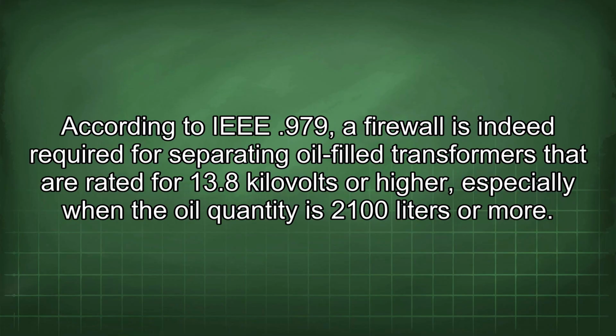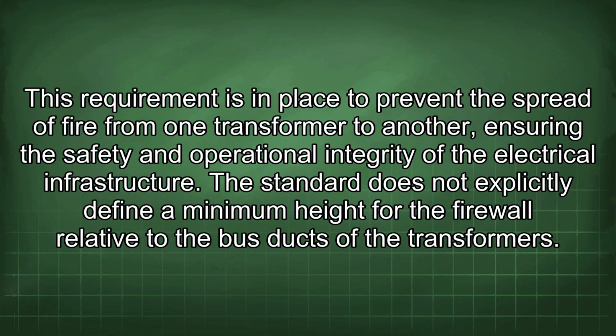According to IEEE 979, a firewall is indeed required for separating oil-filled transformers that are rated for 13.8 kV or higher, especially when the oil quantity is 2100 liters or more. This requirement is in place to prevent the spread of fire from one transformer to another, ensuring the safety and operational integrity of the electrical infrastructure.